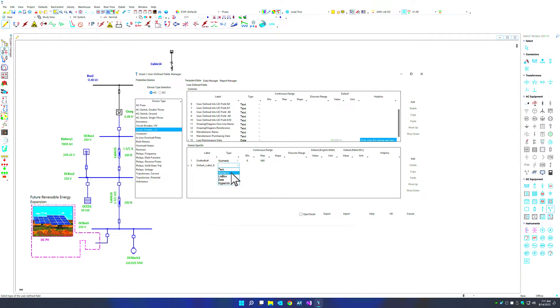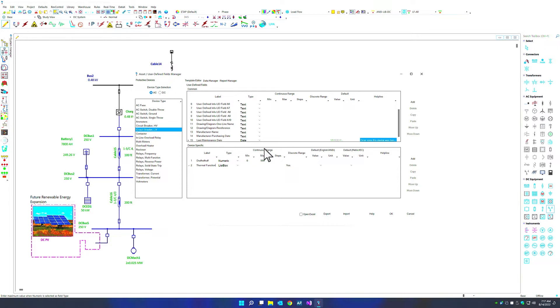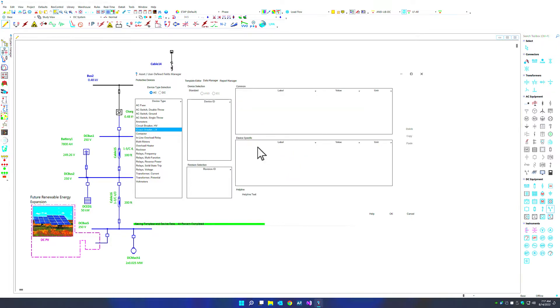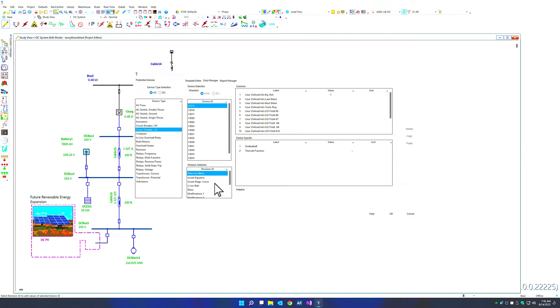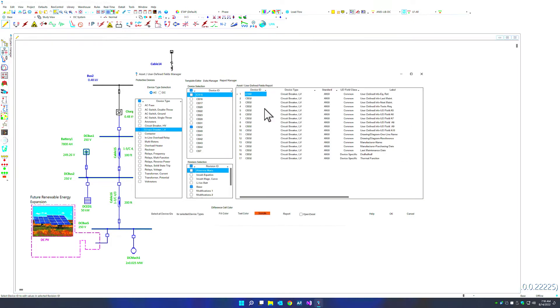We can add another field — a list box with values of yes and no. This could represent something like a thermal function that is part of the breaker but not used in any simulation related to protection or coordination. Within the template editor, you can also go into the data manager to see all changes for those components in base or revision. You can also go into the report manager and export the user-defined fields, including the two new device-specific fields we just added.